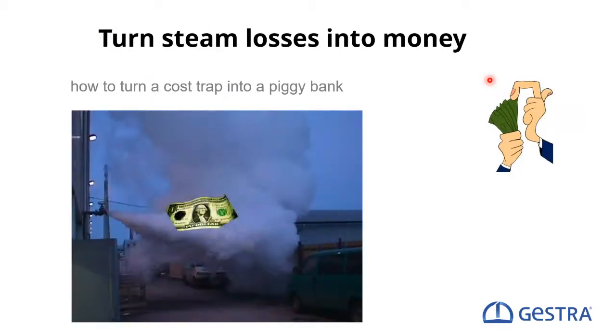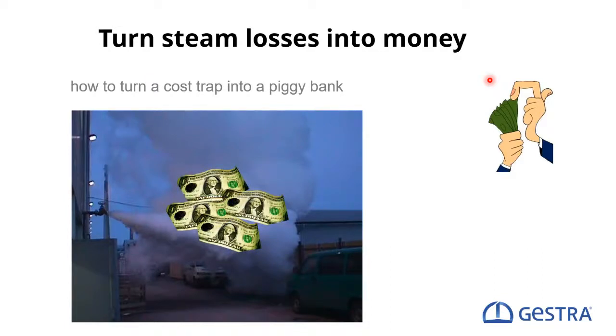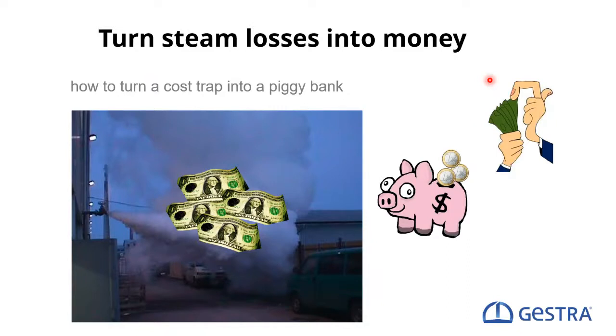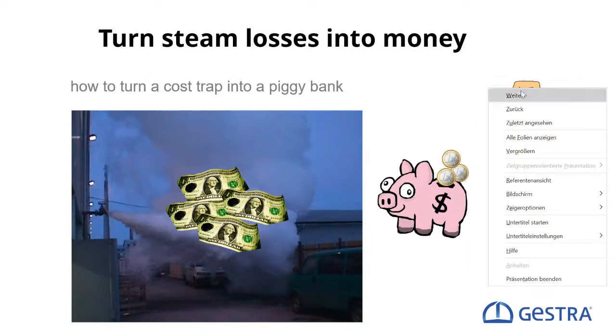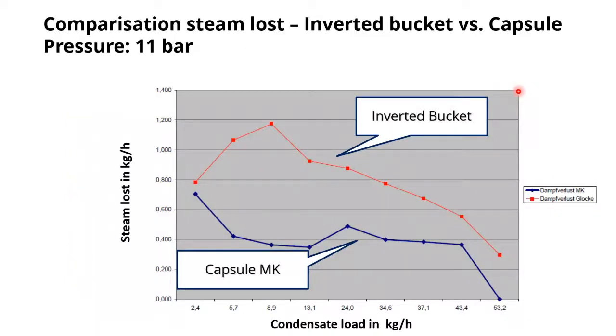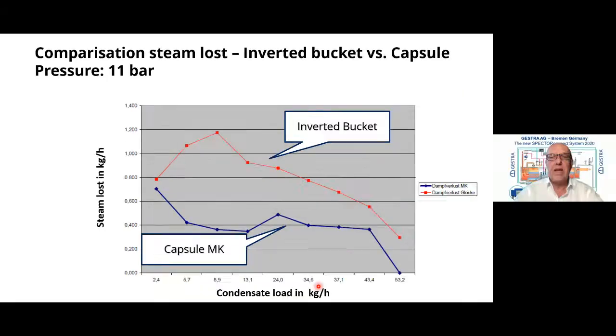Well, the question now is how we could find the most useful trap for our application, considering that we want to save our money. That is the point we have to look for in this little seminar. Steam traps don't have a problem if they have a certain amount of condensate load. If we look here at the condensate load, the more the condensate load increases, the less the steam loss, which we see on the left side, will happen.